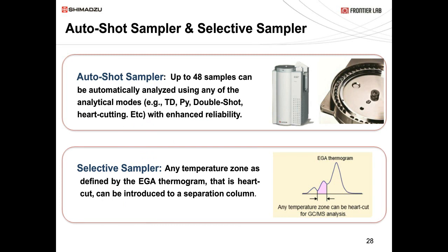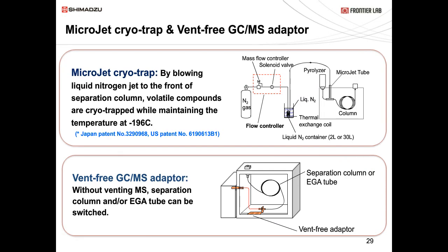The auto shot sampler has 48 spots for your sample and enhances efficiency in your laboratory. The selective sampler allows you to thermally slice your EGA and selectively pick any temperature zone. The micro-jet cryo-trap is connected to the head of the GC column inside the GC oven, using a liquid nitrogen thermal exchange coil, trapping and focusing all volatiles and lighter components—with a lowest temperature of around -196°C. The vent-free adapter at the bottom allows you to switch columns or EGA tube to separation column very quickly in a few minutes.